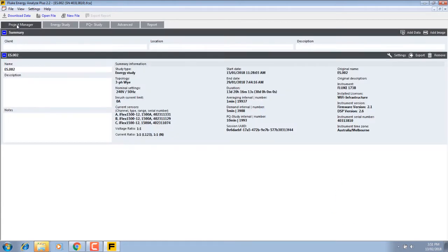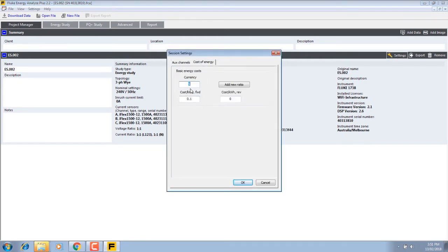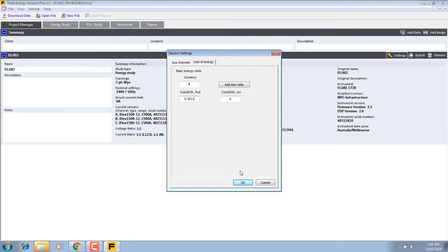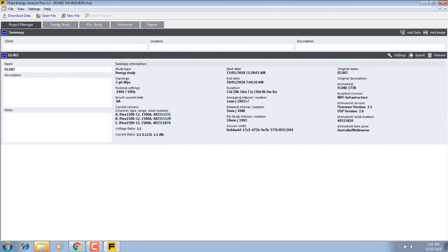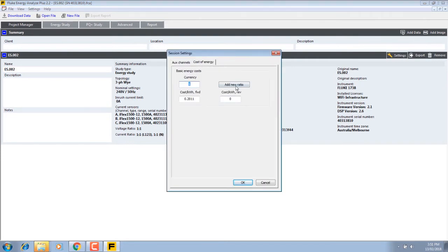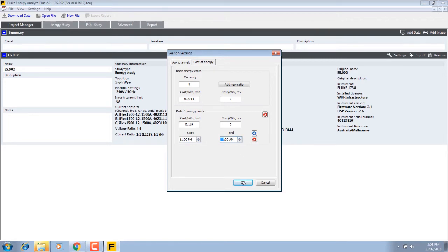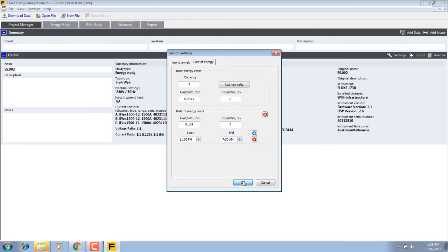Now I'm going to go to project manager, and under settings I want to set the cost of the energy. Our cost here is 20.11 cents. Add a new ratio, and it's off-peak, it's 0.119, and that's from 11 p.m. through to 7 a.m.